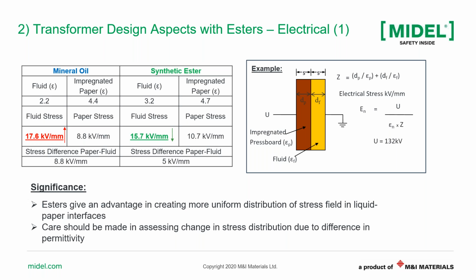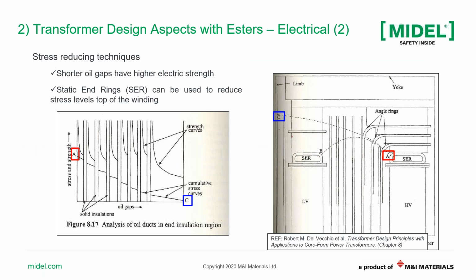But here we need to take care as well, because of this change in permittivity, the entire stress in a transformer will change and some locations will have higher stress. I will talk about this in the next slide. So, as a summary, the significance of this change in permittivity is that esters give an advantage in creating a more uniform distribution of the stress field in liquid-paper interfaces. Between the interface, you have a lower stress. But care should also be taken when assessing the stress distribution within the transformer when we are designing with a synthetic ester instead of mineral oil. And to clarify that further, we can look at this simple system for a transformer. Now, this is a general slide to talk about how we assess the stress distribution within a transformer, and then we can appreciate the impact of the liquid on that.